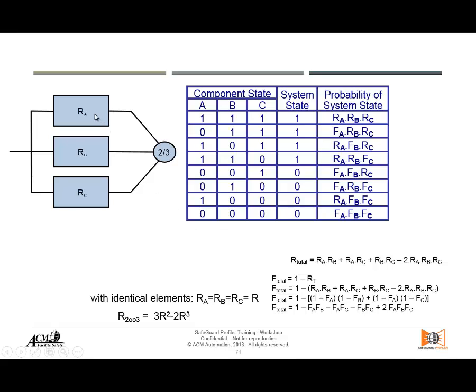For the two-out-of-three configuration, you have three elements in parallel, and the circle specifies '2oo3'. Using the same component state table: working/working/working gives success. Success requires at least two of the three to be working — combinations AB, AC, and BC working all result in success. All other cases where fewer than two work are failures.